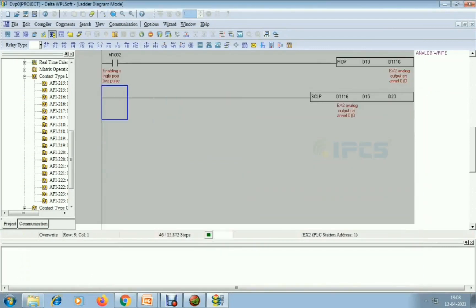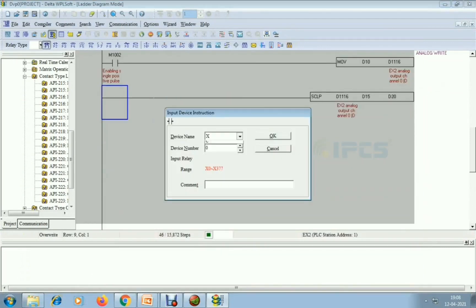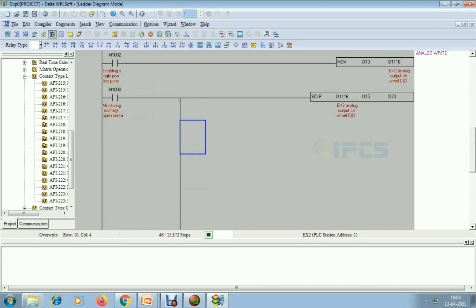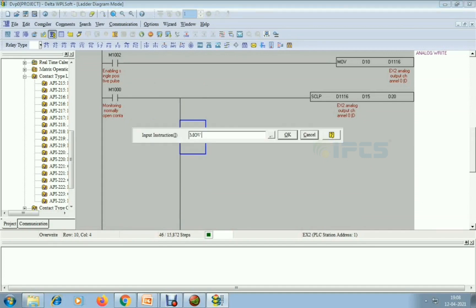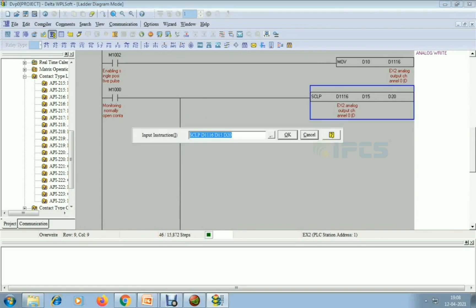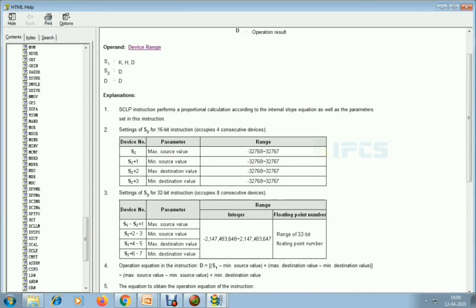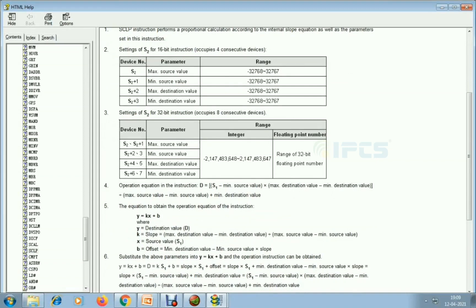Same thing as analog read — I noticed I forgot M1000, so I am adding it now. Next I am using a MOV command, adding vertical lines. The output is 14-bit resolution — not 12-bit — so the maximum source and minimum source values and maximum and minimum destination values will differ.